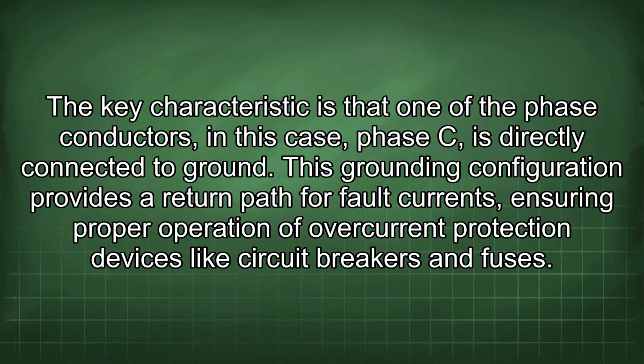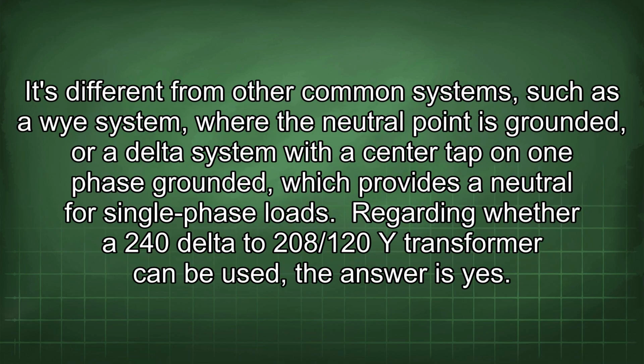This grounding configuration provides a return path for fault currents, ensuring proper operation of overcurrent protection devices like circuit breakers and fuses. It's different from other common systems, such as a Y system where the neutral point is grounded, or a delta system with a center tap on one phase grounded, which provides a neutral for single-phase loads.